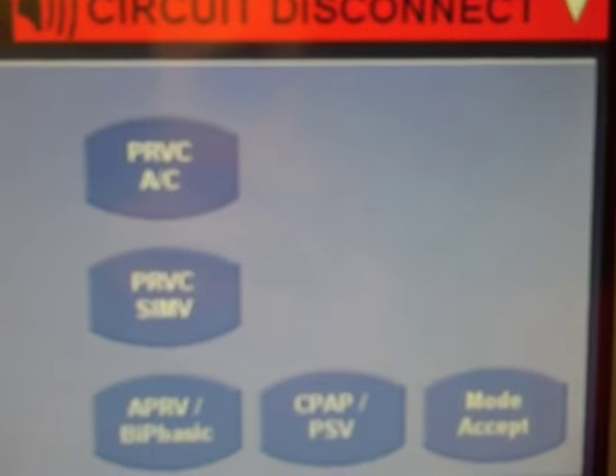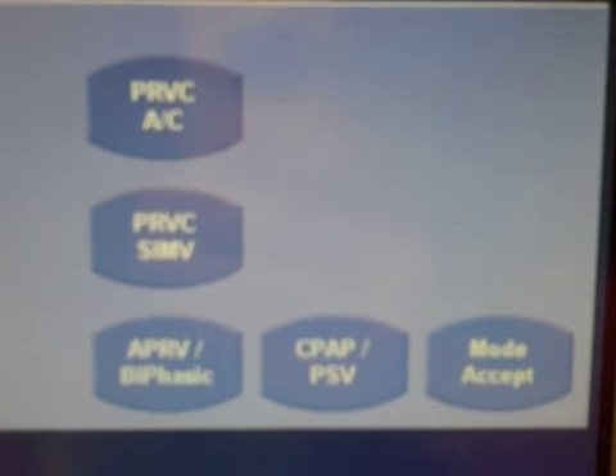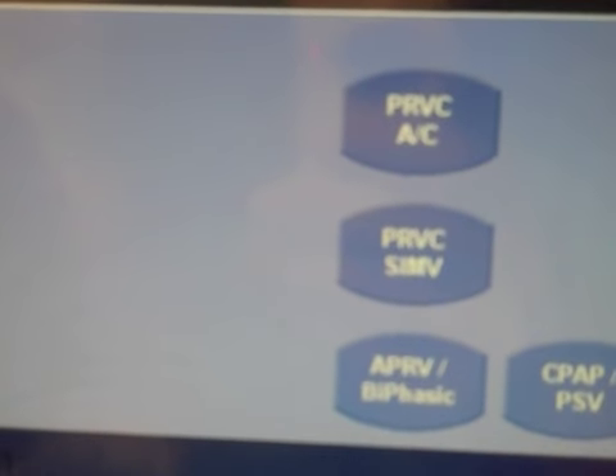And if you want to select your modes, you can touch in the top left here. You've got the choice of volume AC, pressure AC, volume SIMV, pressure SIMV, PRVC AC, PRVC SIMV, APRV biphasic, CPAP, pressure support. And to choose those, let's say we're going to choose a pressure AC, I would choose that. And you can see down at the bottom all the parameters actually come up. So I can go ahead and set my parameters.